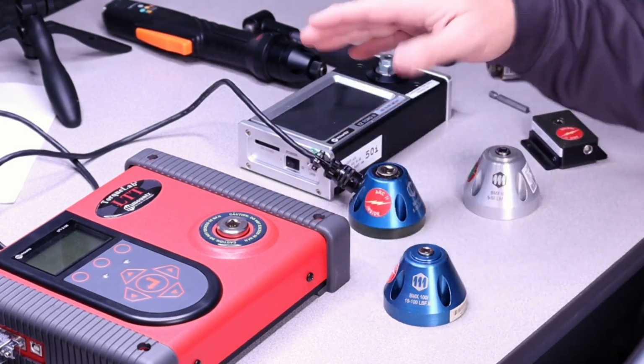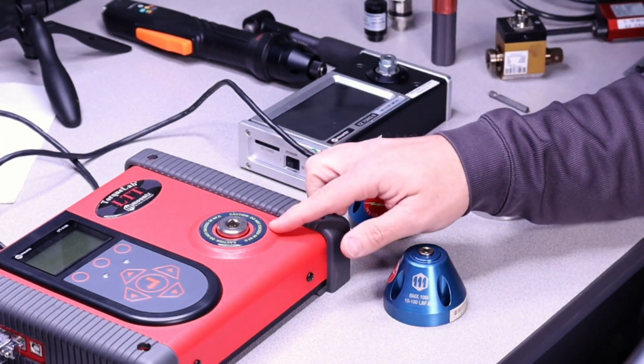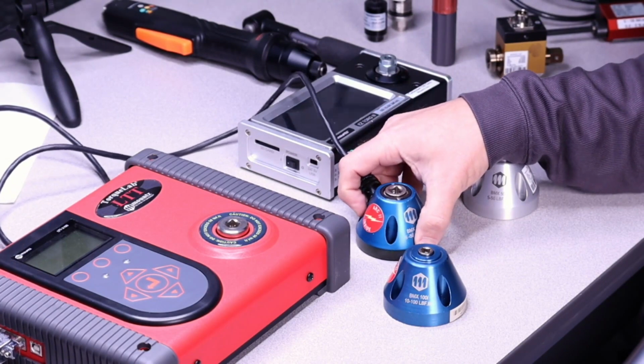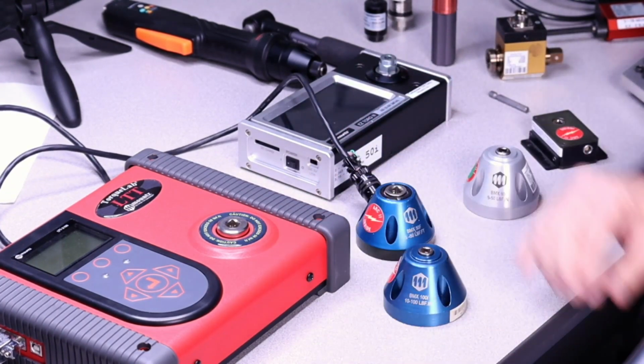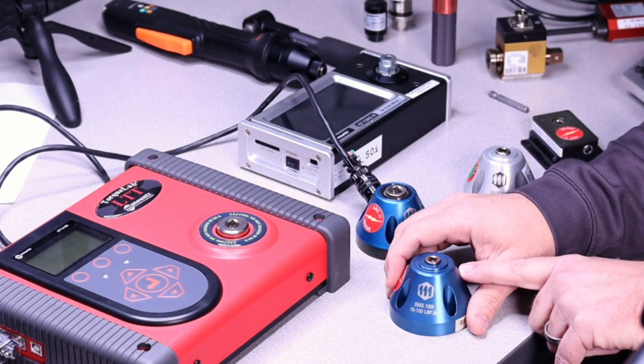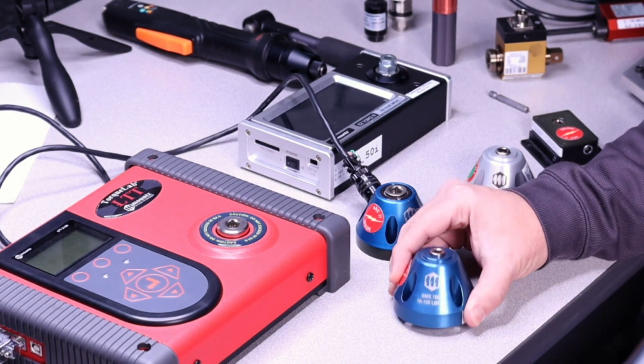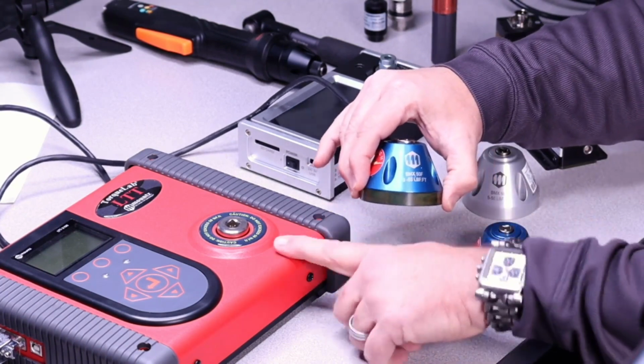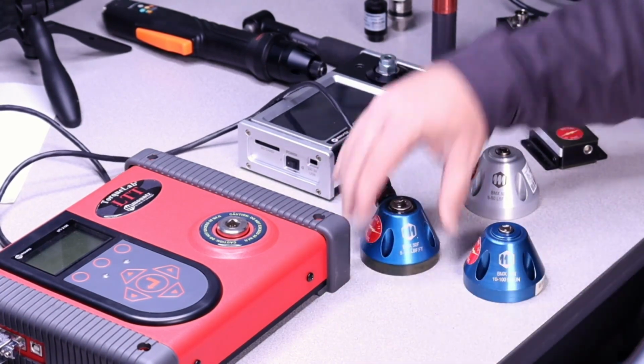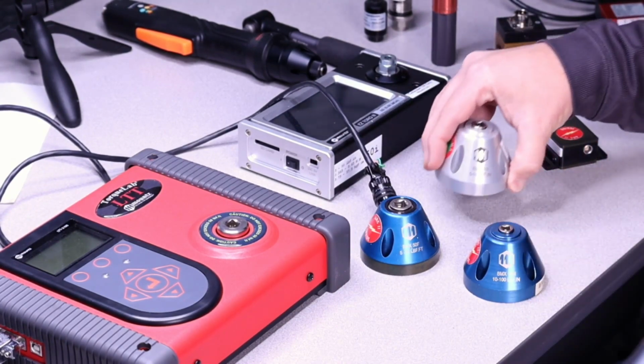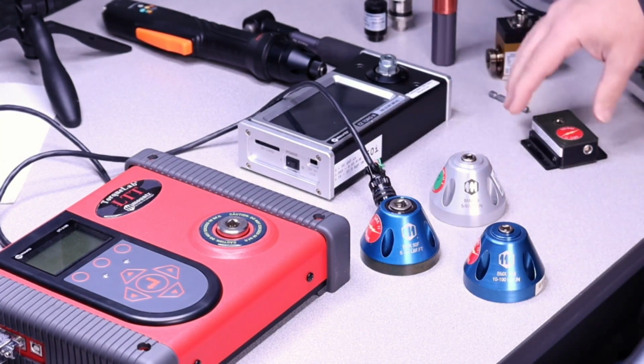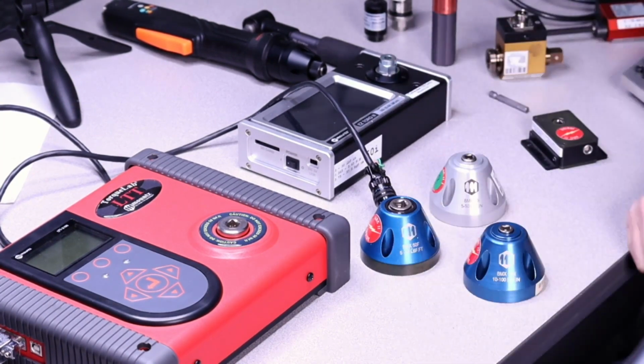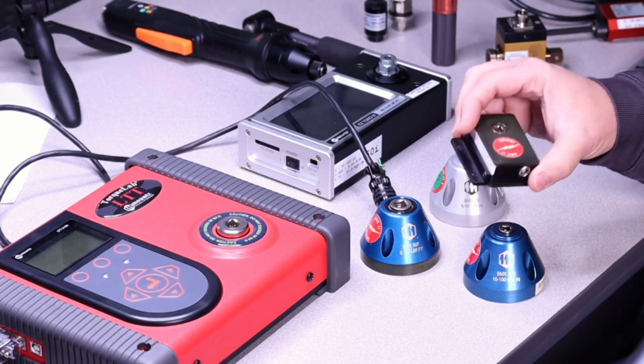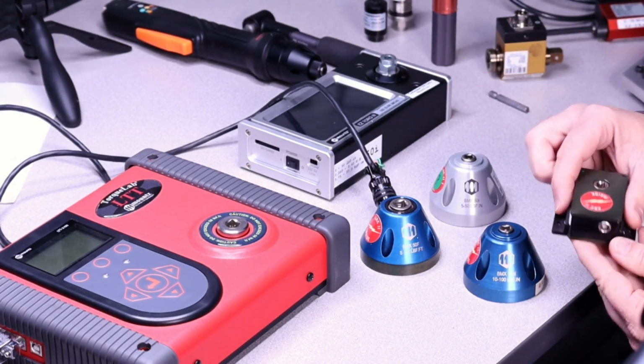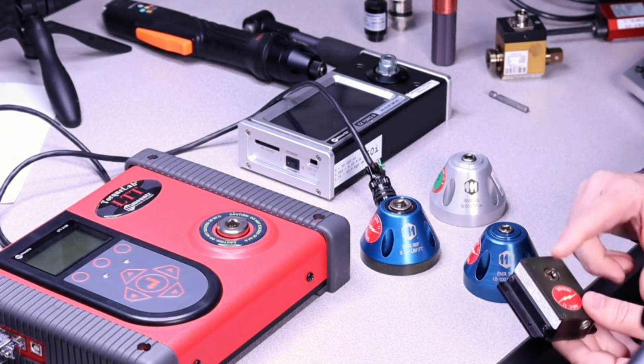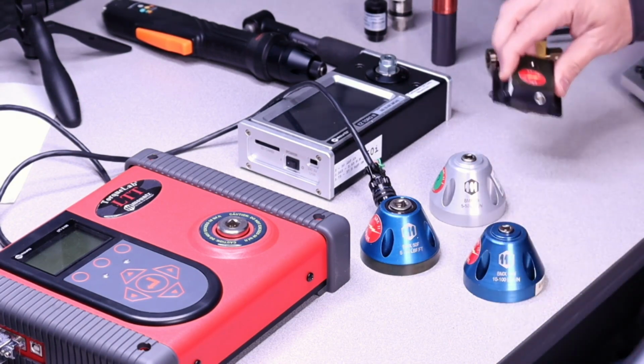The LTT unit has the ability to expand the range of the sensors, so we can add additional sensors that aren't the same range as the internal sensor. For example, here I have a BMX 100i, which goes from 10 to 100 inch-pounds. This one happens to be the same as the internal transducer, 5 to 50 foot-pounds, and we also have a 5 to 50 inch-pound sensor. These can vary all the way up to 10,000 foot-pounds, a little bigger of a sensor. We also have very small inch-ounce type sensors, our MDX type, for very low inch-ounce range testing.